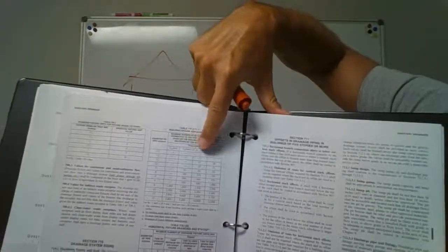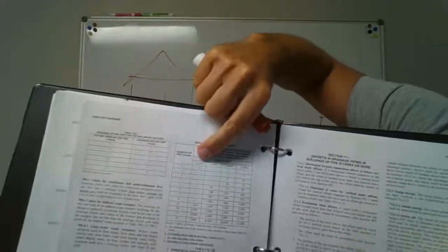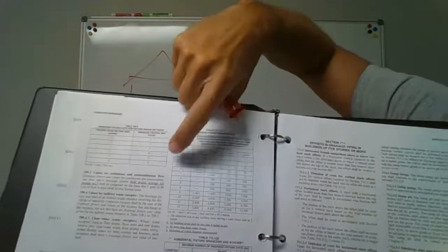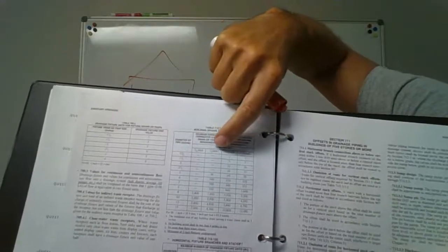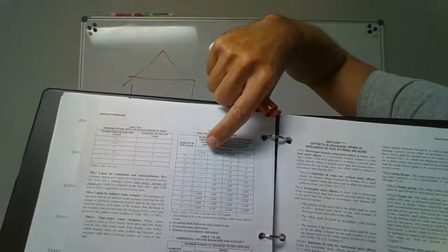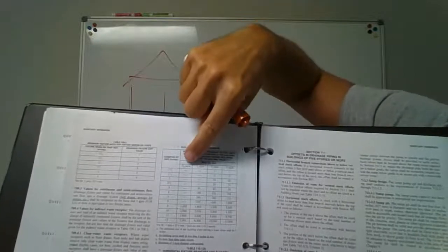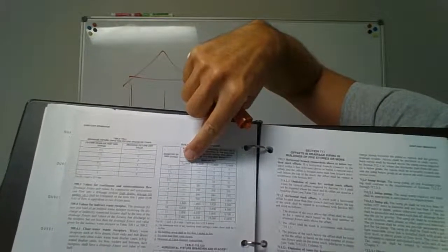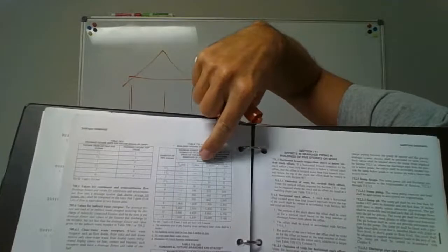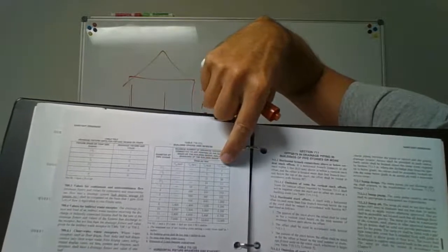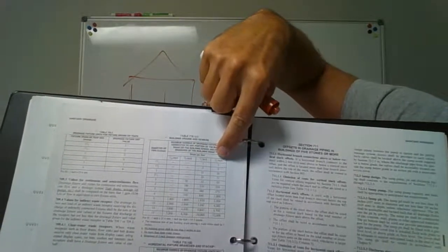But underneath, there are these four columns. The number of DFUs that can be on this size pipe depends a little bit on the slope. Slope is how much of a drop per foot that you have. So a sixteenth inch drop per foot, an eighth inch per foot, a quarter inch per foot, and a half inch per foot is what you're dealing with.